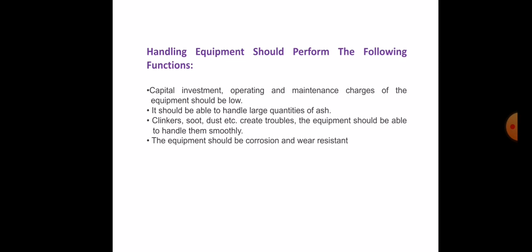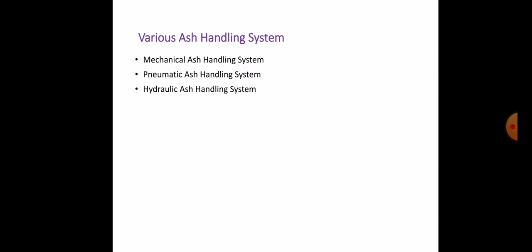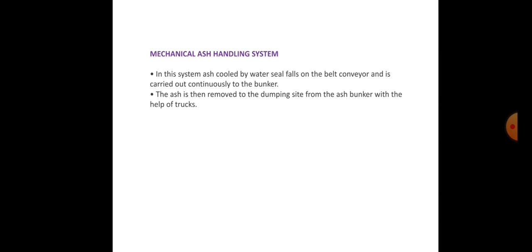Various ash handling systems in a thermal power plant: mechanical ash handling system, pneumatic ash handling system, and hydraulic ash handling system. The mechanical system uses mechanical components, the pneumatic system uses air as the main carrier, and the hydraulic system uses water to collect the ash. Mechanical ash handling system: in this system, ash cooled by a water seal falls on the belt conveyor and is carried continuously to the bunker. The ash is then removed to the dumping site from the ash bunker with the help of trucks.